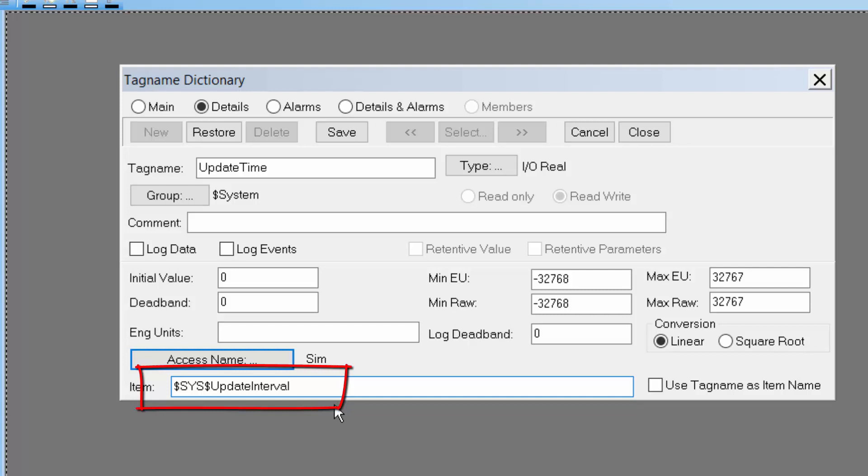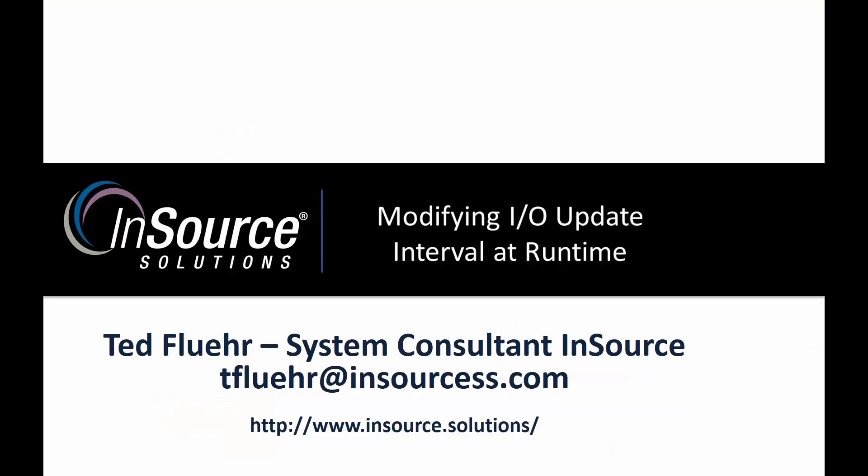So all I/O drivers have this capability, so this is the parameter that I need to write to and it's a runtime variable that I can set that's automatically going to go out and change the frequency that I'm polling the data from my PLCs or my end devices.